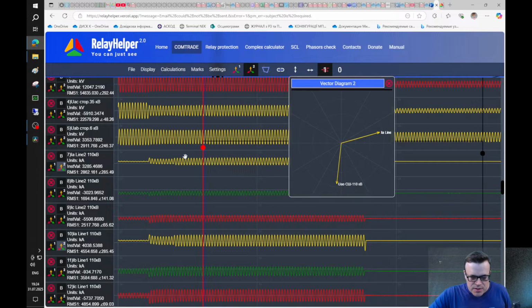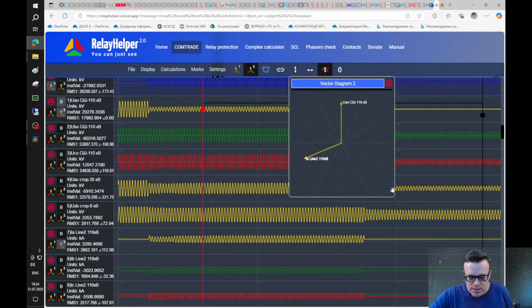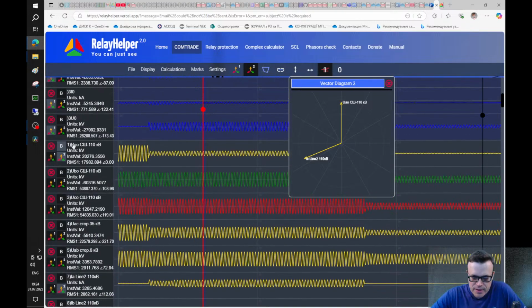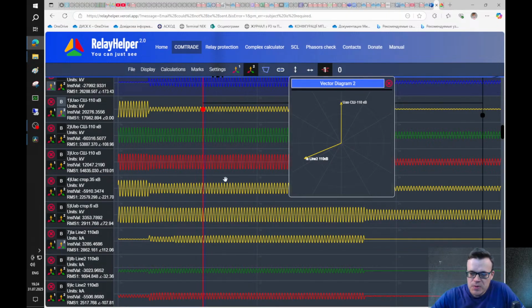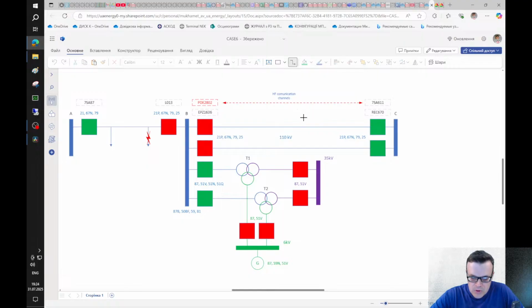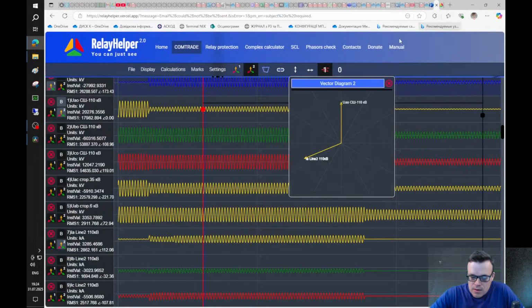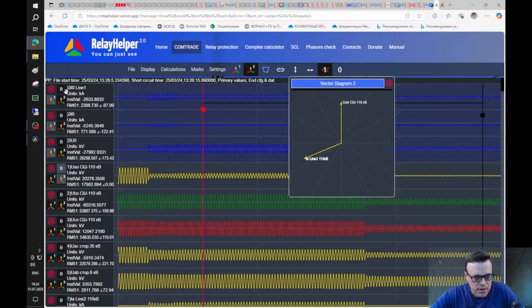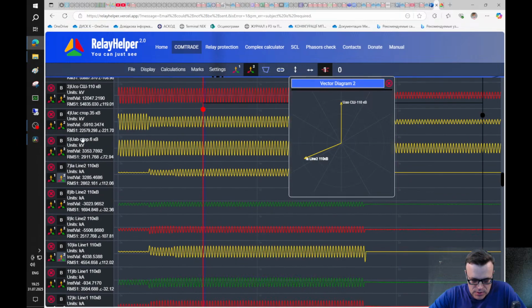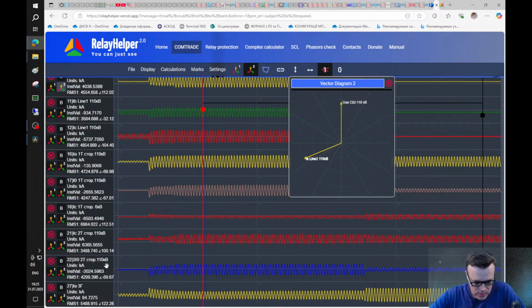But what I want to summarize: if we look at phase currents on the faulted line, we can see that substation B, power plant B, received power from the substation C side. So the power flow was in that direction. So we can look at current on line 1, and because these are 2 parallel lines, we can multiply by 2 and receive the exact value of the currents. So what can we do more?